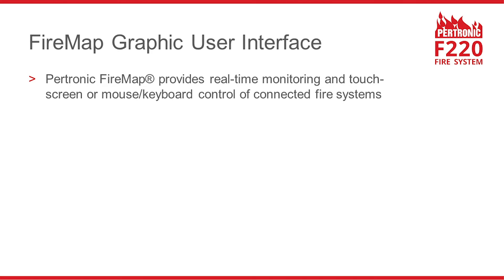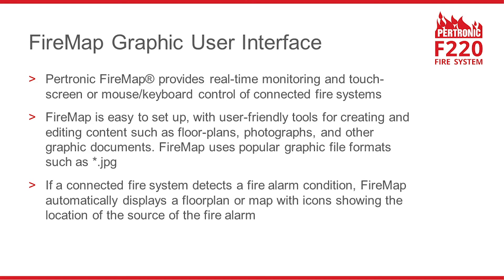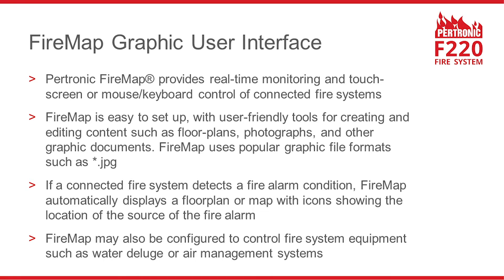Now let's take a look at Pertronic FireMap, the graphic user interface that provides real-time monitoring and touch screen or mouse and keyboard control of connected fire systems. FireMap is easy to set up and has user-friendly tools for creating and editing content such as floor plans, photographs, and other graphic documents. FireMap uses popular graphic file formats such as JPEG. If a connected fire system detects a fire alarm condition, FireMap automatically displays a floor plan or map with icons showing the location of the source of the alarm. FireMap may also be configured to control fire system equipment such as water deluge or air management systems.